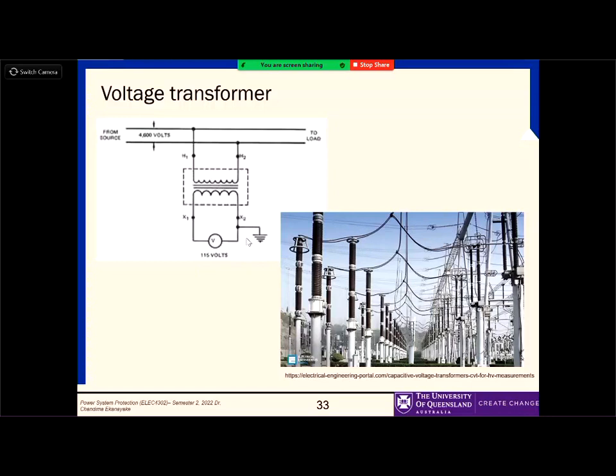Now, usually in real substations, you'll see these columns one for each phase. I'll come to that - if some of you are not familiar with three phases, I've included a couple of new slides to give a brief introduction to three phase. In a real power system it's usually three phase, so you'll have one column for each phase. If you look here, only one wire is connected, so that's the easiest way to distinguish a VT from a CT. In the CT you could see two wires, one coming in and one going out, but here it's the same wire, and the voltage is tapped here.